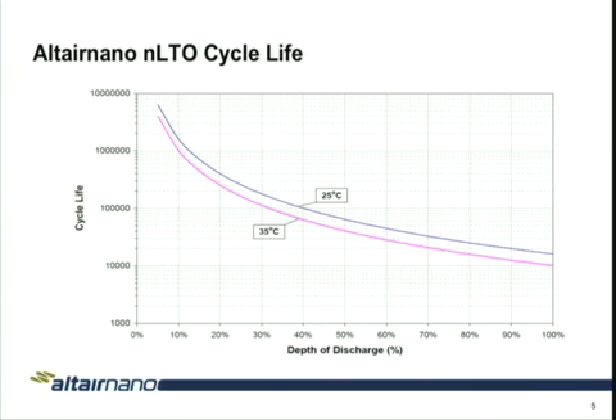I asked a couple of questions this morning, all about life cycle assessment. And what does that mean to a battery, right? How do we have a battery that can provide a lot of power or a lot of kilowatt hours, but if it doesn't last, there's going to be a challenge on cost effectiveness. In this case, for our batteries, we're talking about 16,000 full depth of discharges. It's a logarithmic scale on the side for cycle life, and then depth of discharge on the bottom here. And you can see how it ratchets up as you have a shallower depth of discharge.